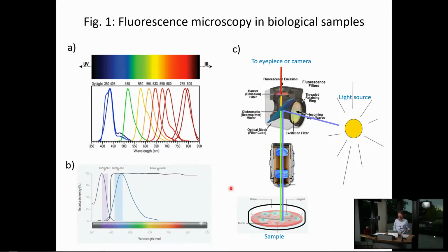So just to come back to this Stokes shift, what you see down here is a dye molecule that has this excitation spectrum, so it will absorb over this range here, roughly between 350 and 400 nanometers, and then it will emit somewhere around here from 400 to 500 nanometers, whatever that is. And what you want is a clear separation between emission and excitation, so that you can use filters that will pass what comes through here and will clearly distinguish between the excitation and the emission.